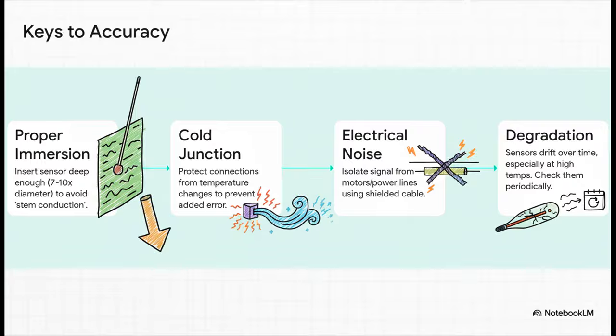3. Isolate from electrical noise. Thermocouples create a teeny tiny voltage signal. If you run those wires right next to big power cables, that electrical noise can completely scramble the signal. And finally, number 4, account for degradation. Sensors are not immortal. Over time, especially in high heat, they wear out, they drift. You have to check them and replace them on a regular schedule.